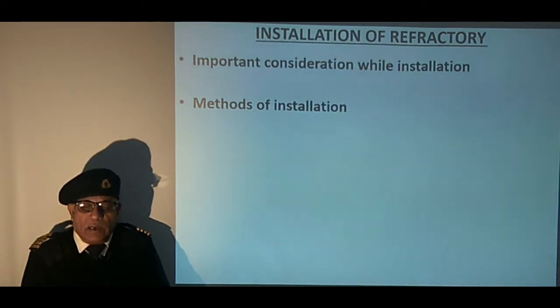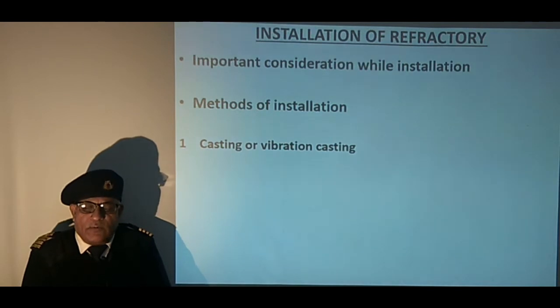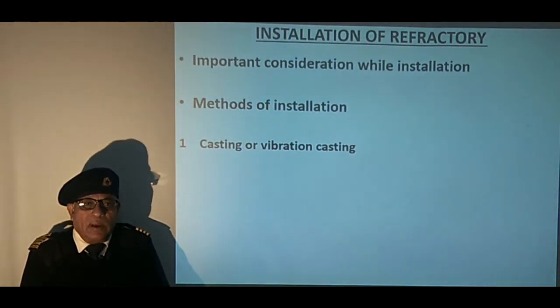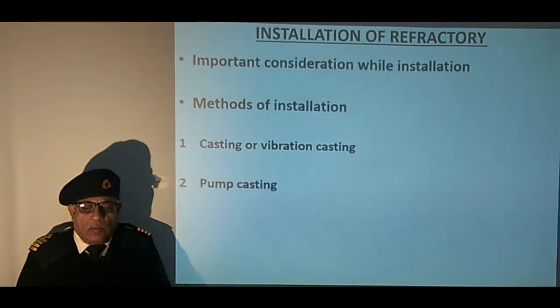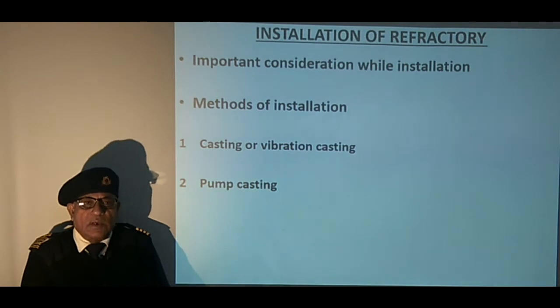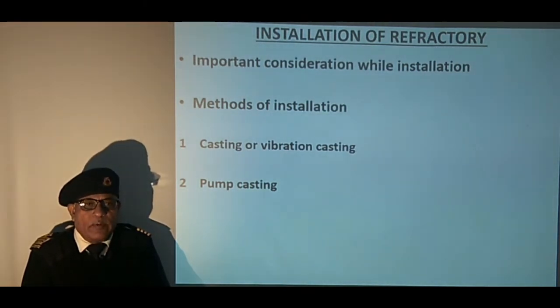Monolithic refractory can be installed by one of the following methods. The casting method is the straightforward method of mixing and pouring wet material into moulds which hold it in place until it is set, and then the moulds are removed. As the castable refractory is in a fluid state, most types of castable refractories can be pumped to a location by special trucks or trailers equipped with pneumatically operated screw pumps with pipes and hoses.